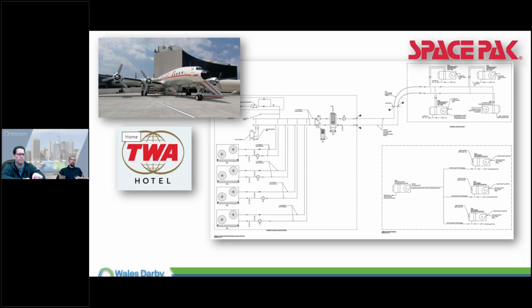But efficiency-wise, we just took a whole tank of 120 degree water and dropped it to 44 degrees, and then we have to reheat it again on a heating coil. So if we have these mixed heating and cooling opportunities, having dual buffer tanks is not a bad thing - a cooling tank and a heating tank. You can draw off of them independently, and the outdoor unit will maintain the temperature in them depending on which one needs it.